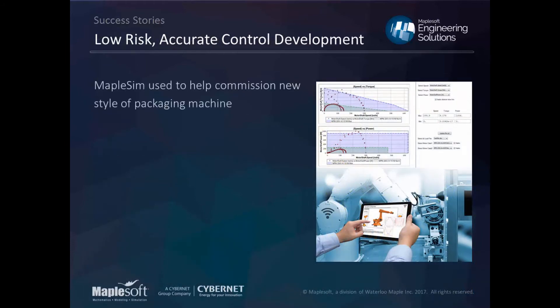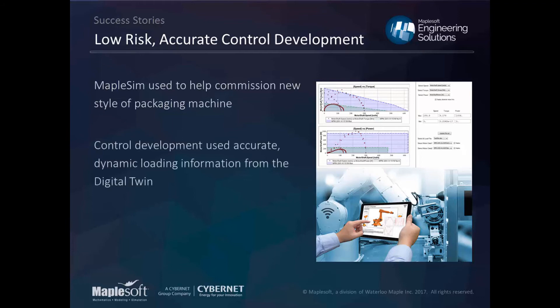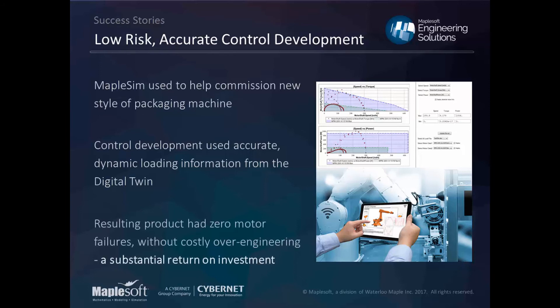A quick example from the machine design world: a customer was getting motor failures after shipping their products. Deeper analysis showed they were missing spikes in current draw on the motors — their commissioning phase test cycles all passed, but the product failed earlier than predicted. The issue was that they were using Excel for static steady-state analysis, so they weren't capturing detailed enough accelerations and actual torques the motors experienced. By using our software to test upfront, they were able to adjust the motion profile rather than add a bigger motor, and were much more confident the failures wouldn't recur.